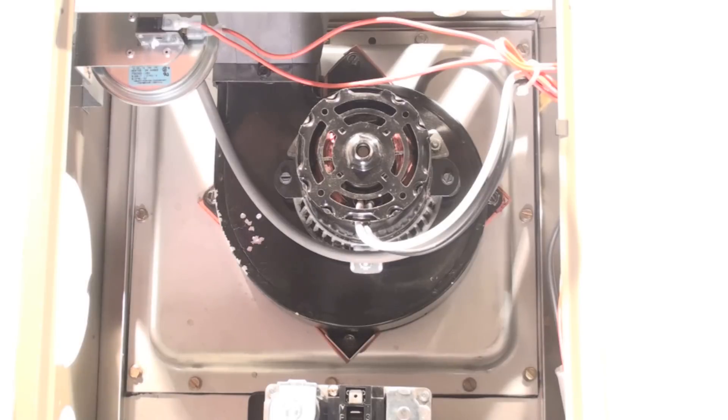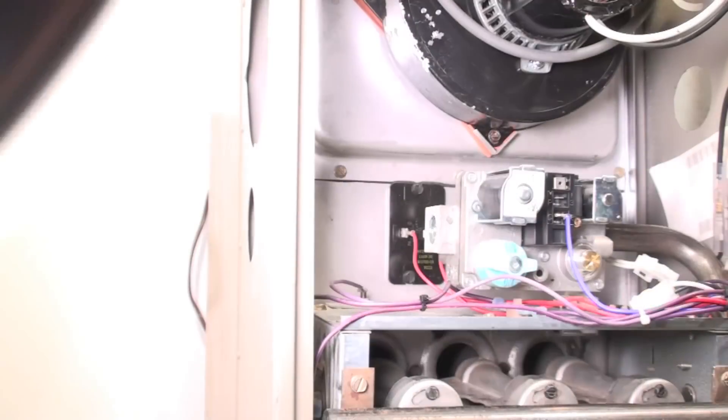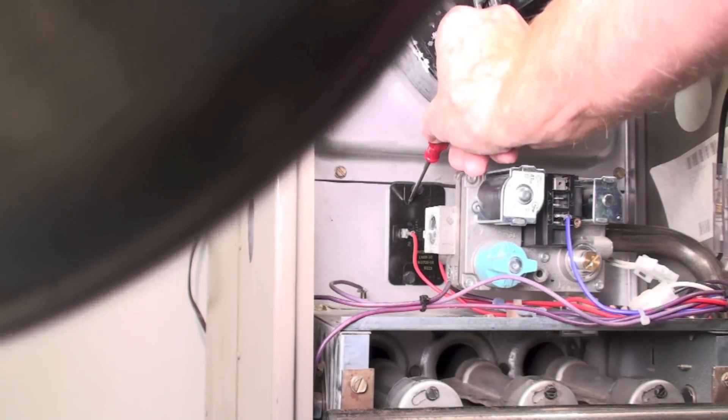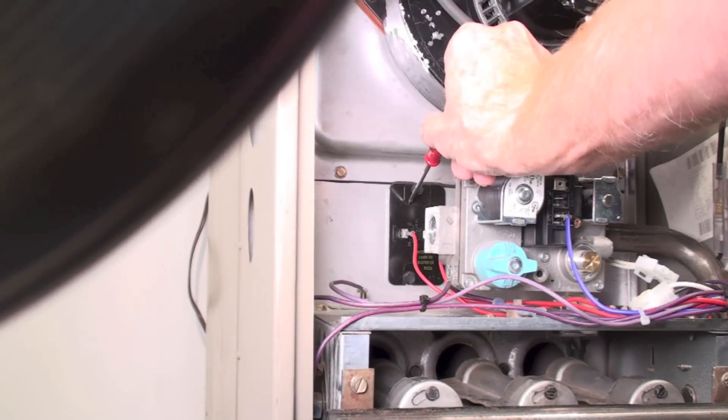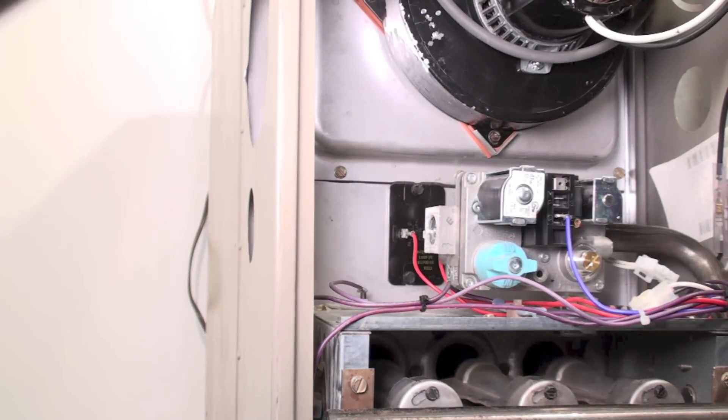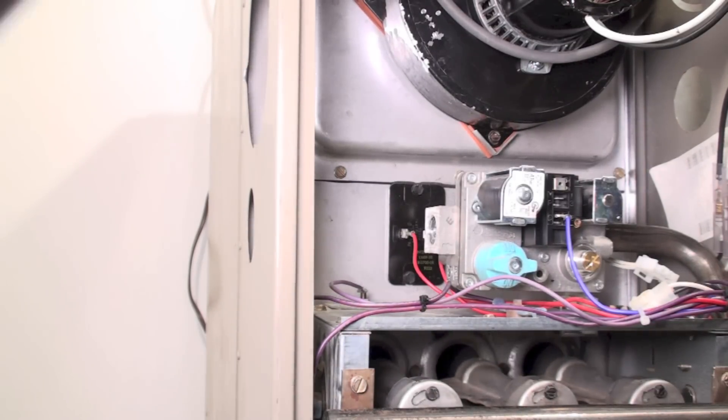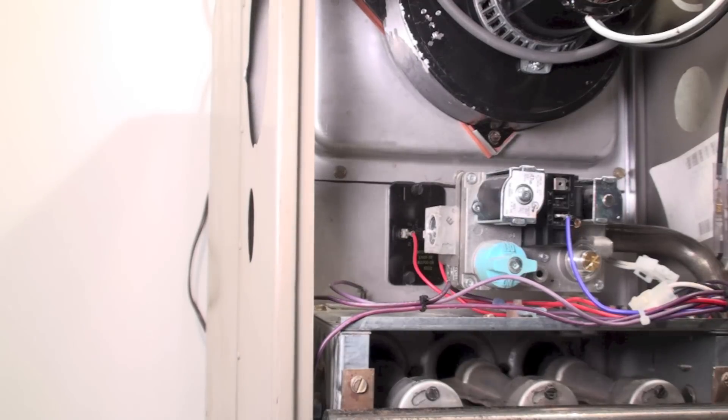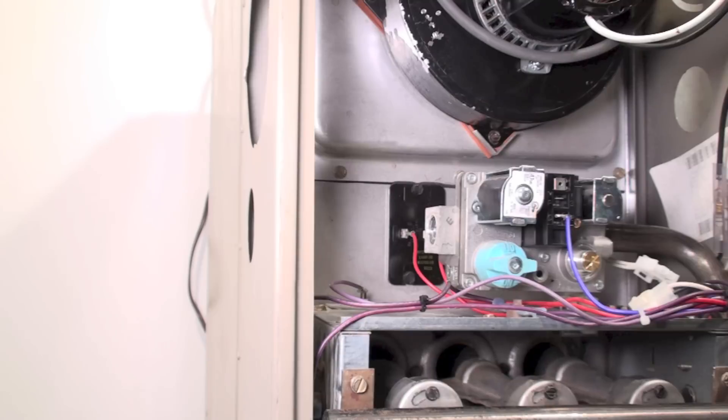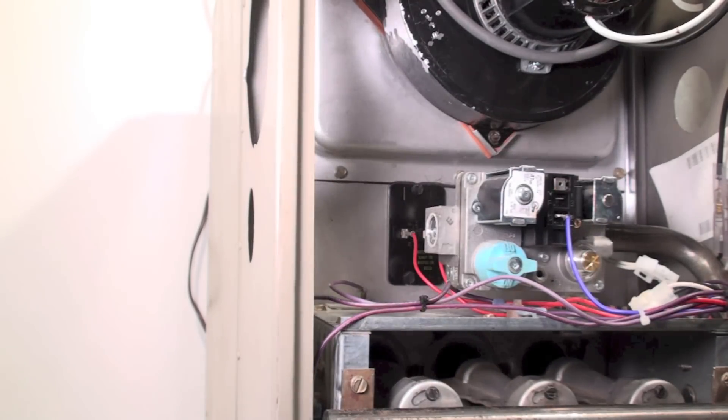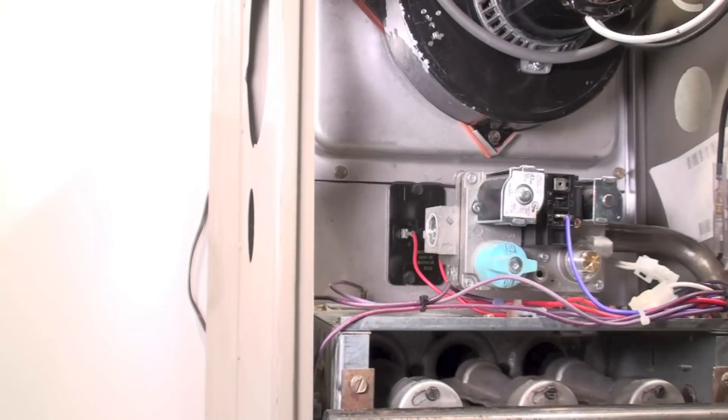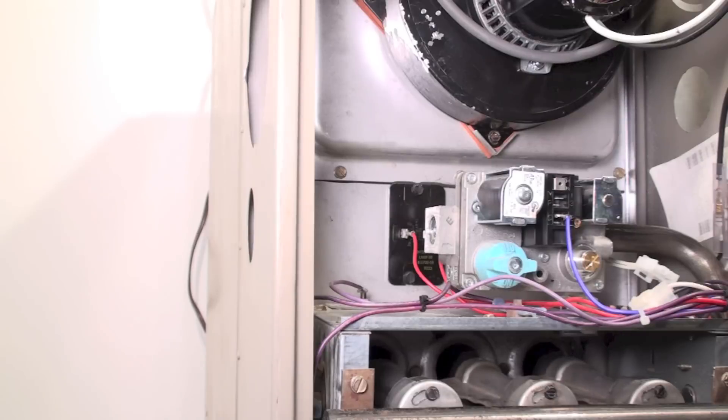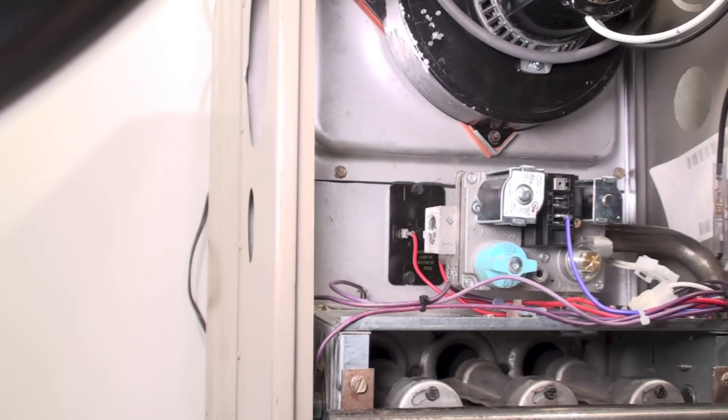The next thing it's going to do is look at the limit switch. This is a limit switch right here. After that inducer starts, it's going to look at the limit switch and see if it's open or closed. A limit switch is a high temperature safety. If it's open, it goes no farther and goes out on the limit switch code failure, also turns the fan on.